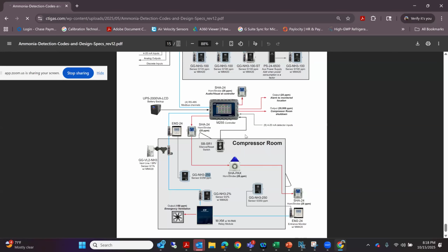And of course, having the reset button inside the compressor room, that is code. You're supposed to reset this system from inside the compressor room after a leak is mitigated. And so you'll see a lot of the reset switches being inside the compressor room. Sometimes if the controller is in the compressor room, then they're covered.